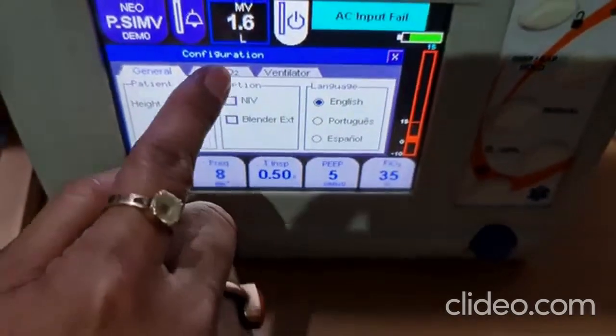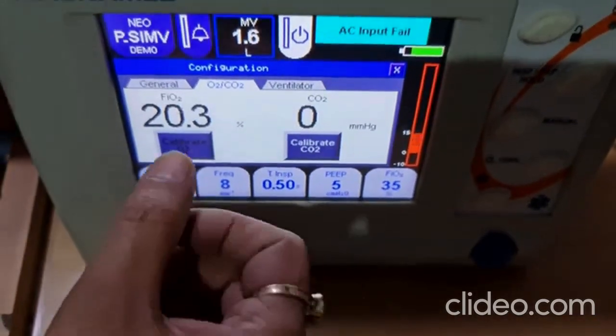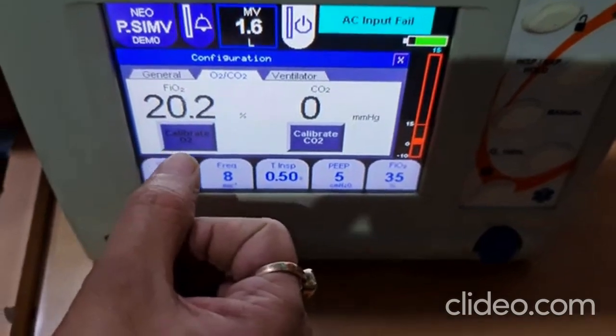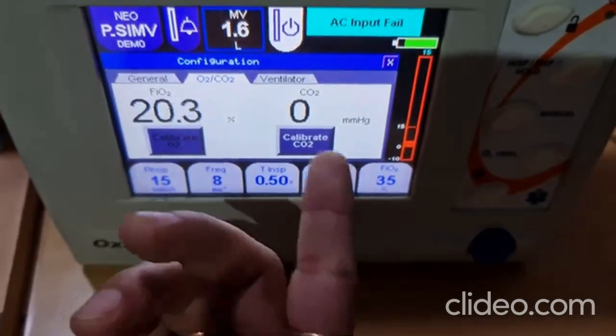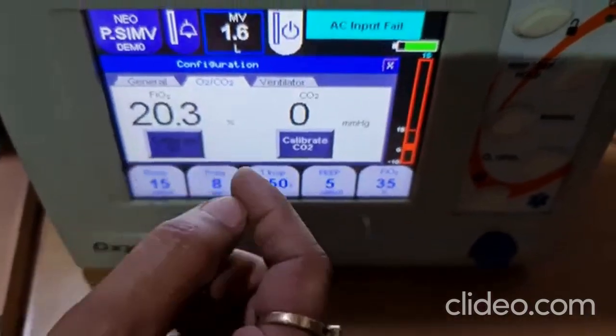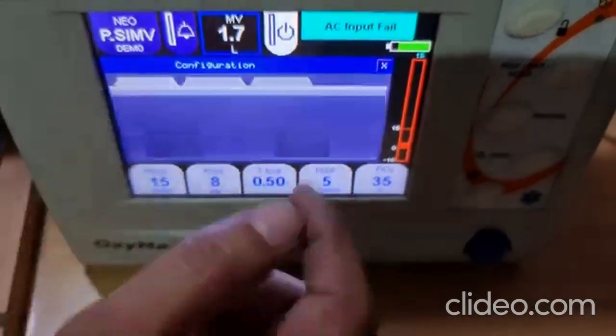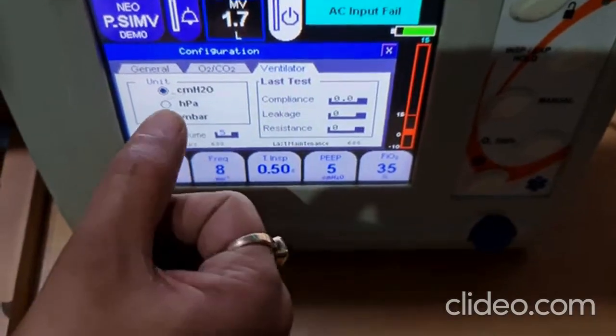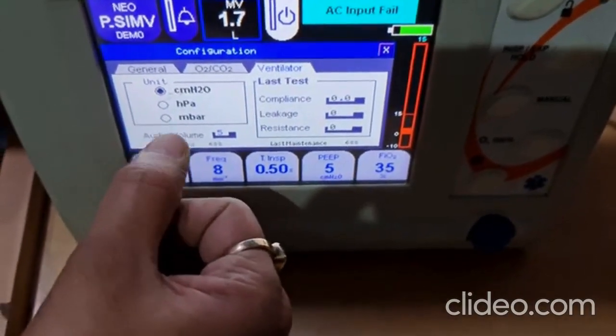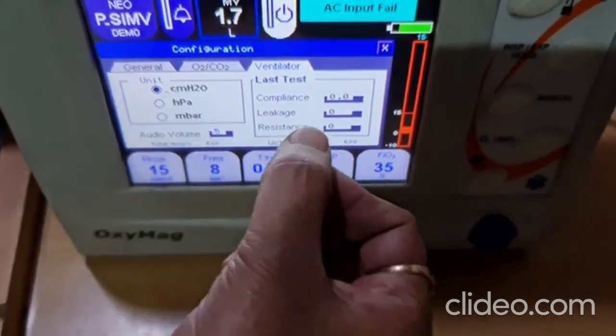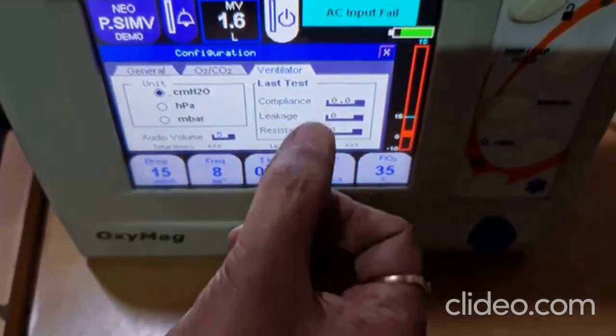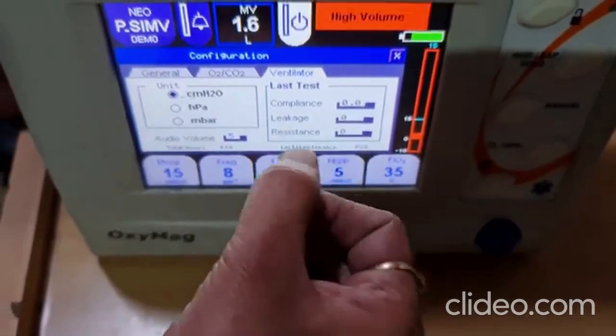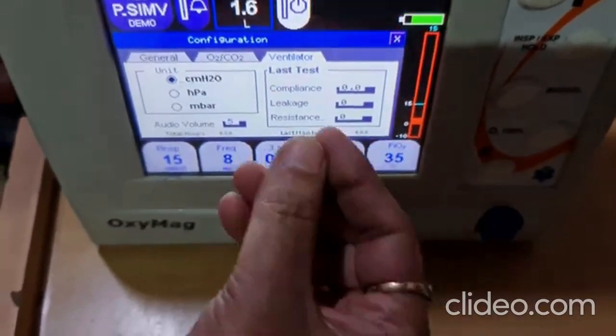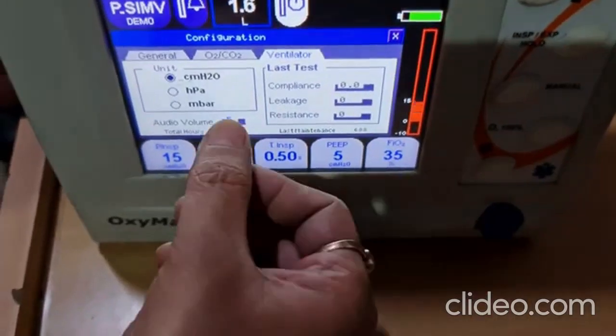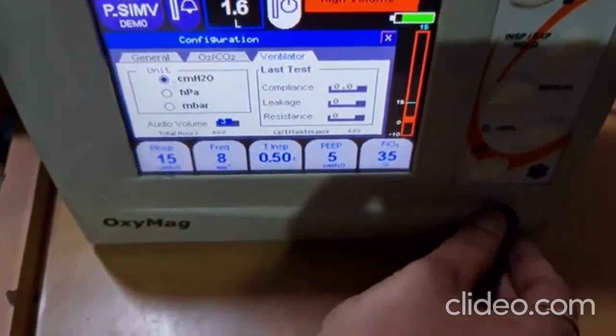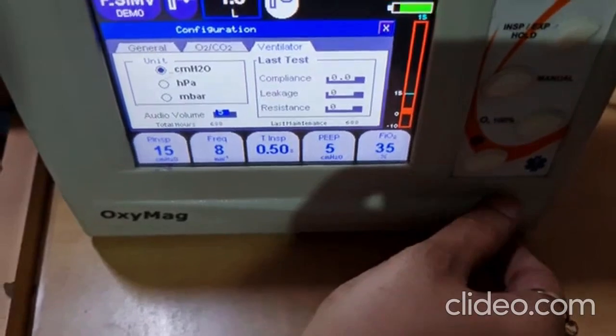Next is, here you can calibrate oxygen or CO2 if you want to calibrate, if you are using the CO2 sensor. Next is ventilator. In this you can change the units of the pressure. Here you will get, when you test this ventilator, you can get all this compliance, leakage, resistance of the circuit. You can also get that. Here you can adjust the alarm volume. The 5 is maximum, 1 is minimum.